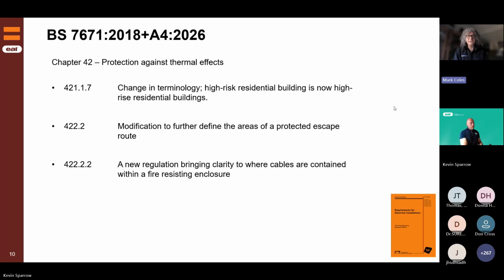Then 422.2, modification to further define the areas of protected escape route. And 422.2.2, a new regulation bringing clarity where cables are contained within a fire-resisting enclosure. This was about the introduction, a number of iterations back, I think the last iteration of the Brown Book, of the protected escape route. You might see these kinds of things in football stadiums, a very bare, bleak, concrete escape route. There's nothing in there other than basic things like a handrail, steps, and lighting, maybe a fire alarm system, but anything in there has to be sufficiently fire rated.